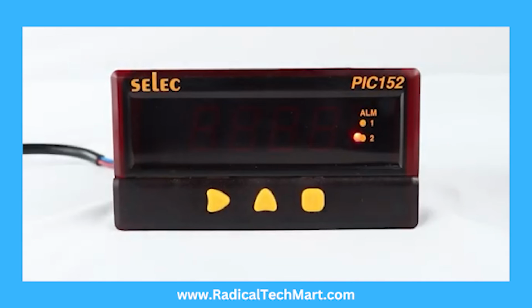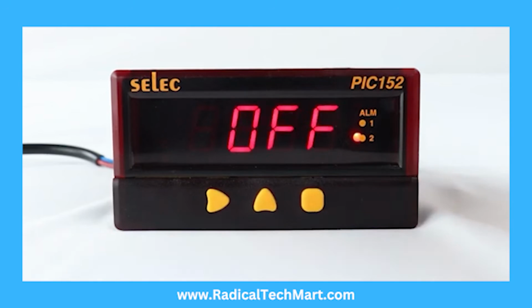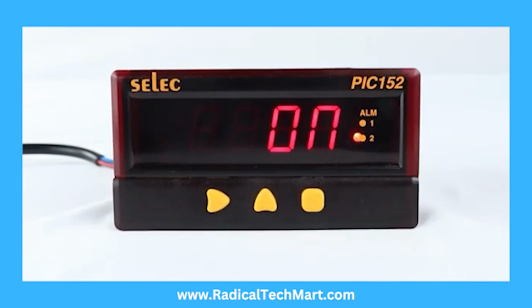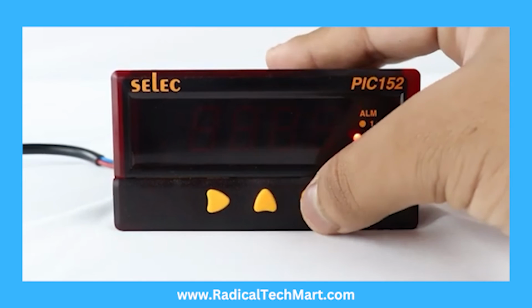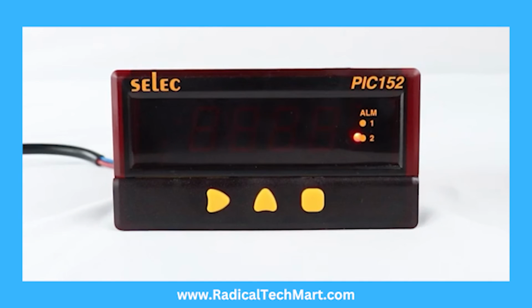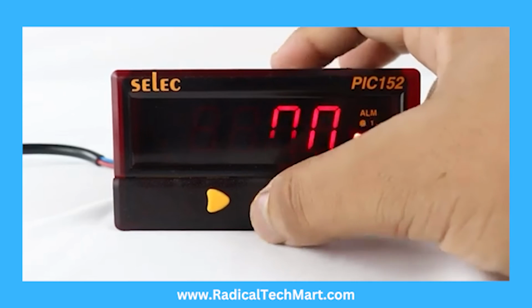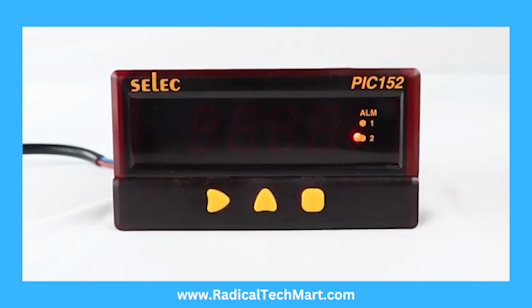Now alarm latch status. In on condition, the alarm is latched until it is acknowledged manually, even though the alarm condition may have disappeared. Then, alarm hold status. When selected on, it prevents an alarm signal on power-up, and in off condition, it does not prevent an alarm signal on power-up.